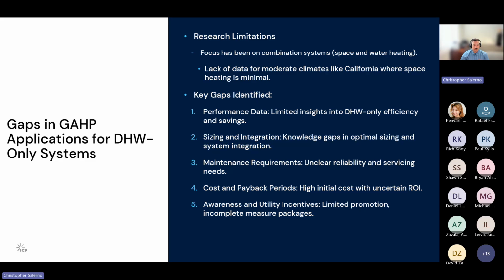So firstly, performance data, there's limited insights into domestic hot water only efficiency and savings, so not including space heating. And then also sizing and integration. So at the beginning of this, there was really little knowledge to know how to size these gas-fired heat pumps specifically for domestic hot water applications, and then properly integrating them into the system. And then the third would be maintenance requirements. It was really unclear since contractors were not very familiar with this, not at all used in California for this type of application. It's unclear about the reliability and what the servicing needs will be from the manufacturer or the contractor, servicing contractors.